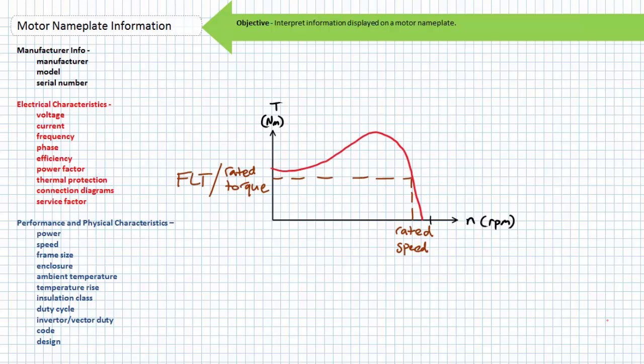As we'll learn in later lectures, the rotor of a three-phase AC squirrel cage induction motor, the most popular industrial motor in the known universe, must necessarily lag behind the natural speed of the rotating stator magnetic field, even under no load conditions. The natural speed of the rotating stator magnetic field is known as synchronous speed and is a relationship of input AC frequency and the number of pole pairs per phase. Given the rotor already rotates slower than synchronous speed for unloaded conditions, one would expect at full load conditions the speed would be even less than this unloaded speed.